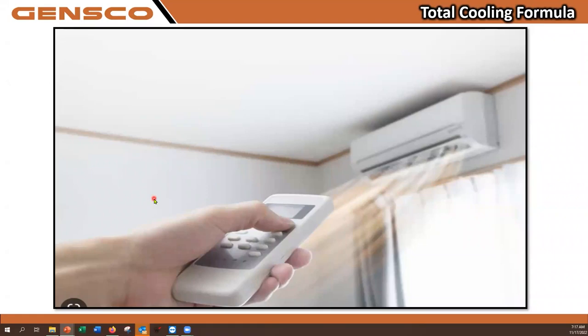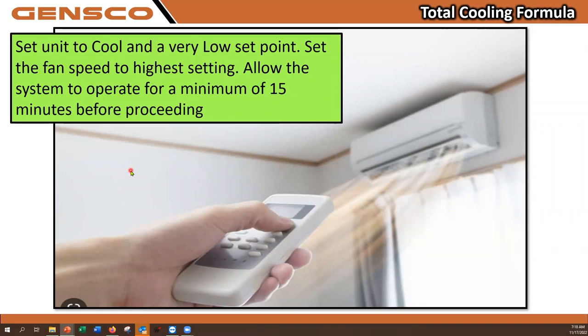We're going to turn the unit on again, just as we did in heating, and we want this unit to go as low as we can in cooling. If the room is already fairly cool, you would probably want to press the emergency op button on the front of this unit one time to put it in cooling test mode, so it will stay running and not reach the set point. It'll run in that mode for 30 minutes, and it will not care how cold it gets in the room. So if you're doing this in cooling and it's already cool, you may want to use the test button. Otherwise, just setting the temperature as low as it can go may not be long enough runtime. And again, we want to allow at least 15 minutes for the outdoor unit to speed up and get to its steady state efficiency before we take any temp readings.